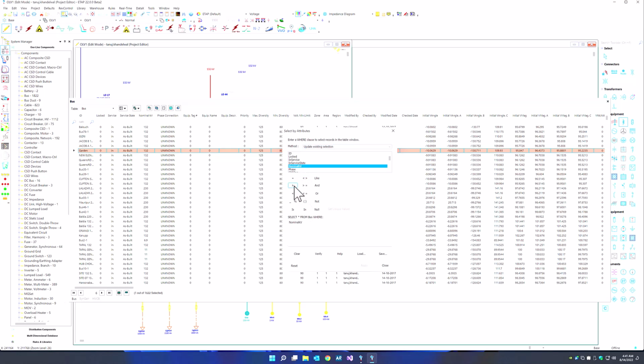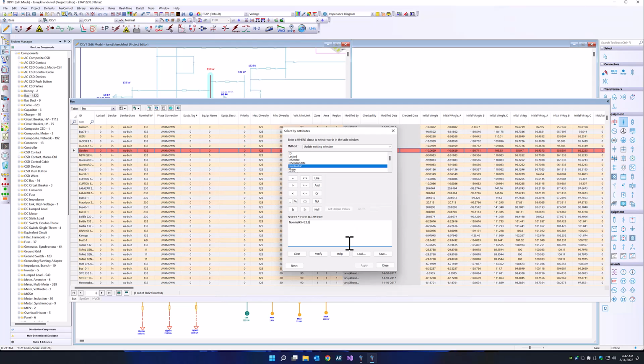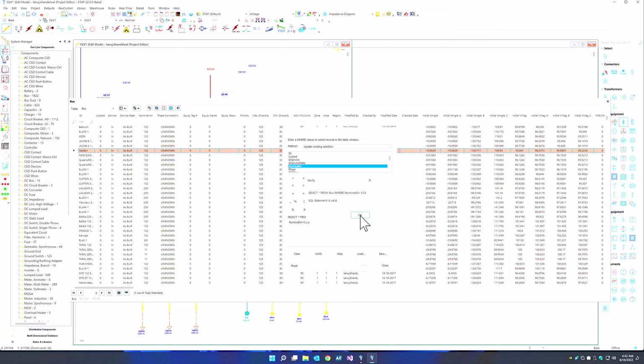You can put the parameter and the value that you would like to compare it against. Verify that the query is valid and execute it to find the components based on the criteria you're looking for. An example could be finding buses less than a certain voltage. Another criterion could be finding all the single phase components in the system, or it could be as basic as finding relays or fuses in the system that don't have any library associated with them.